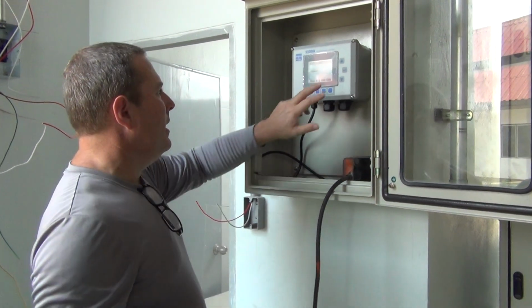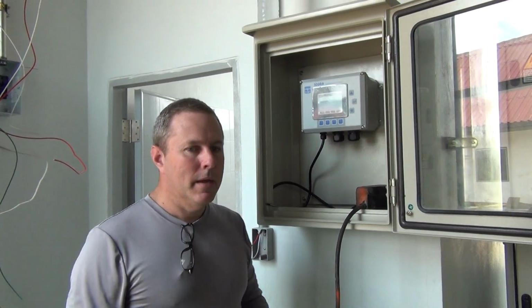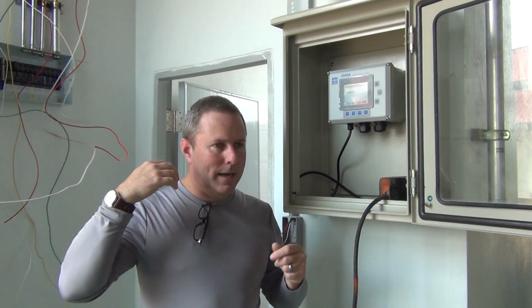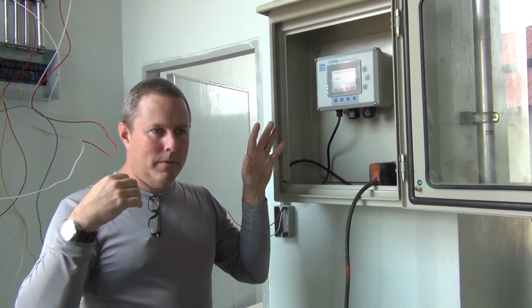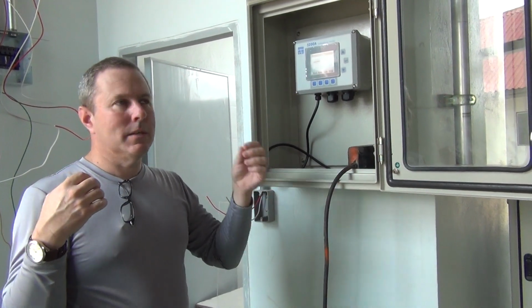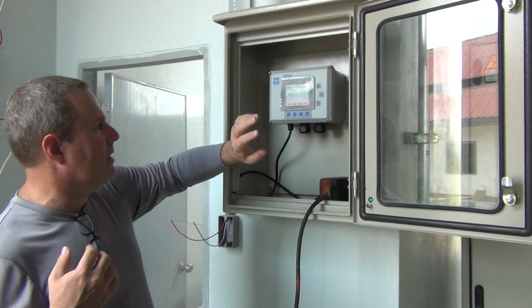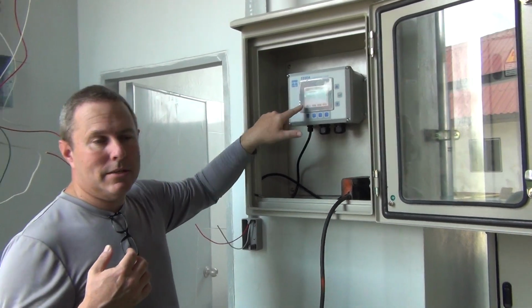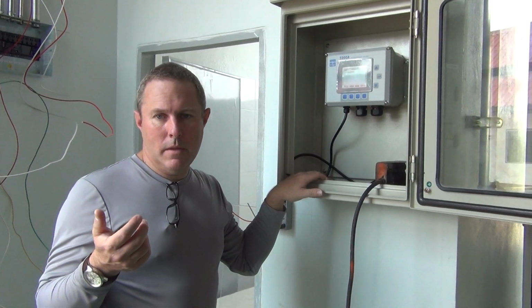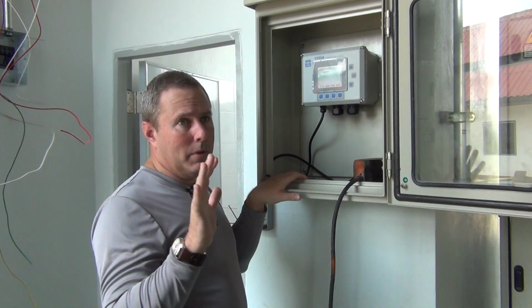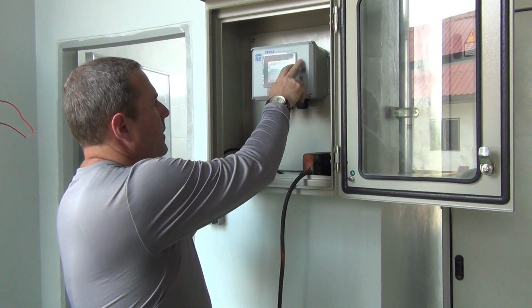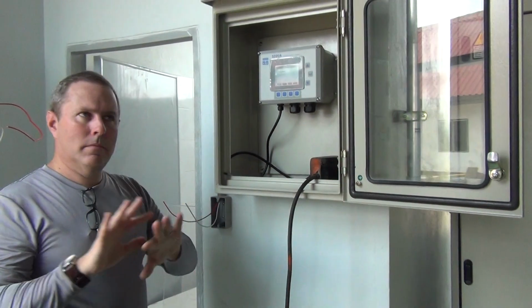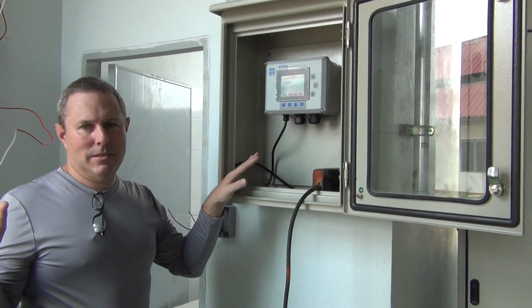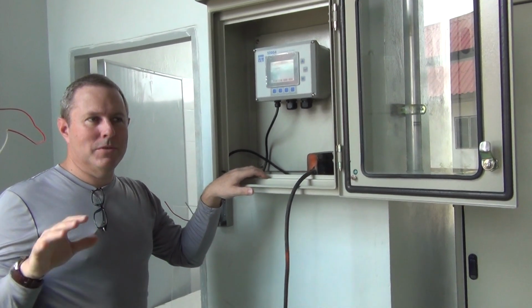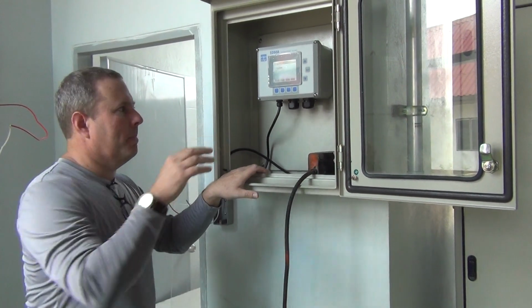Okay. If you have a problem with a sensor, I would suggest you call either YSI or myself. I would say, hello, okay, please go to menu system, to service, to reset to factory, reset sensor, and then I would tell you to reset a specific sensor to see if this solves the problem. Okay. Very rare, not normally going to be used. Then, reset system. Should not need this. If I have to do this with you, something is wrong. Something is off.